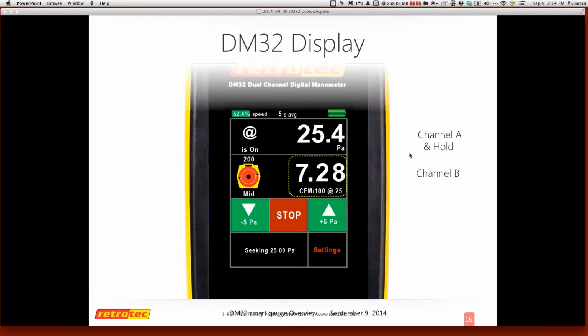Channel B is below. That's going to give me my results. They can be in CFM. For a duct tester, it can be CFM per 100, per 1,000, for 1 square foot, 100 square feet, 1,000 square feet, a variety of options you have for your results. And that was intended to help you with code compliance. The blower door will also do air changes per hour. And as many of you know, those are calculated from a number, which we'll discuss on how you find that and where we get that.